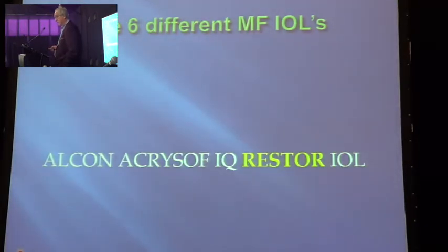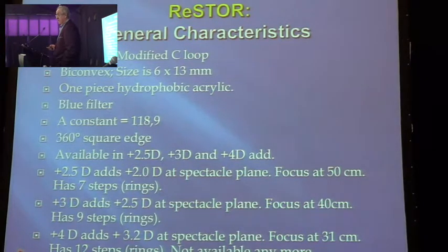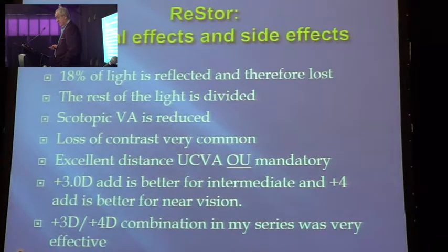Let's go back to the initial lens. We all know the ReSTOR lens from Alcon. I'll talk about the unique optical qualities: it's bifocal with a central diffractive region. It's apodized, meaning the diffractive step heights become less, and there is a peripheral refractive region. Look at the light distribution: 41% for far, 41% for near, and 18% reflected or lost. Side effects like all the others — scotopic vision reduced, loss of contrast very common. It's very critical that you have good far vision for these patients; if distant vision is wrong, the patient is unhappy.